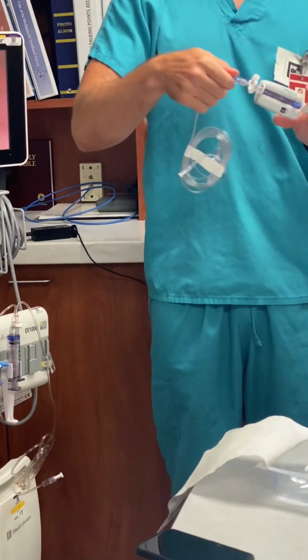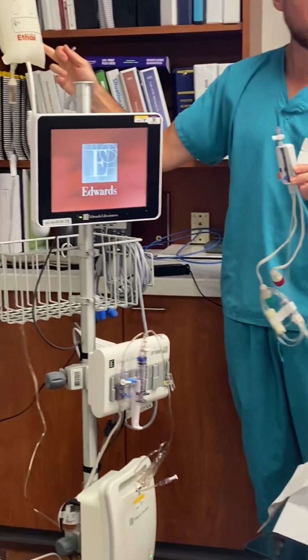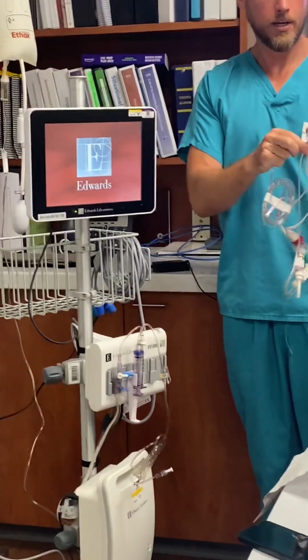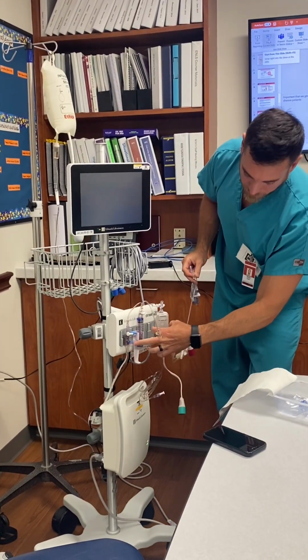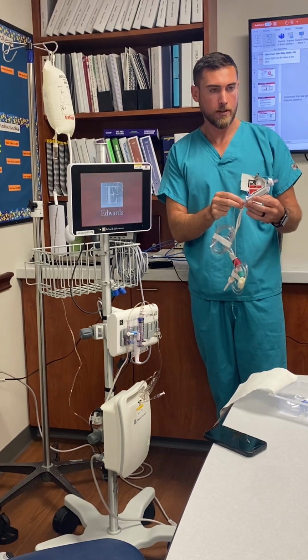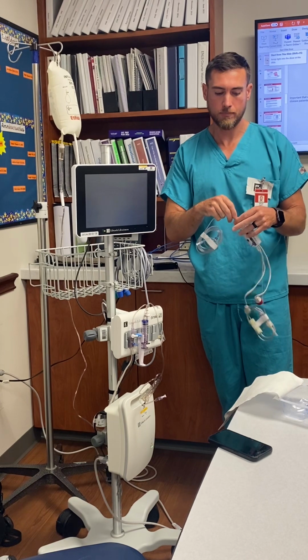So if your patient does already have an existing arterial line, again, maintaining aseptic technique, you could disconnect this, hook it up to your pressure bag, prime it through, and then put this into, right here, replacing this little transducer, if that makes sense. And I'll do that again once this is powered up.